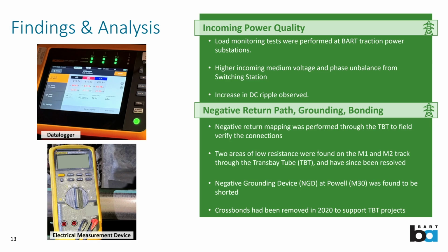And what was very interesting is that at MTW, the incoming voltage was higher than expected. And if you can squint enough, you might be able to see that on the A phase, it was 815 volts, and then 810 on the B and the C phase. So this is not the 34.5 coming in, because the loggers were installed on the secondary side of the transformer, in between the transformer and the rectifier. So that line-to-line voltage should be 783. So that's how we know it's higher.